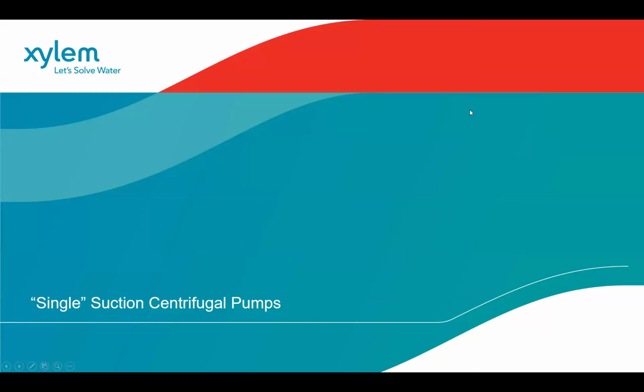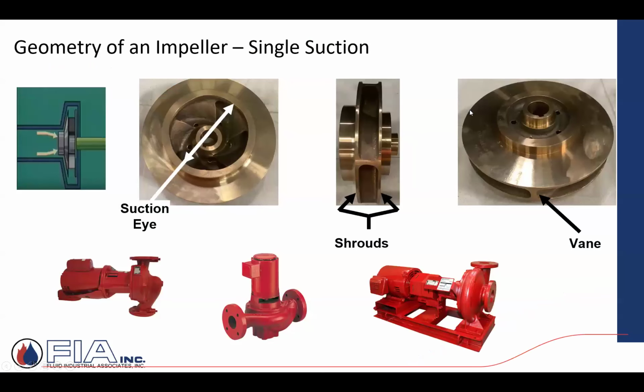So you get into a couple of different style pumps. The first one, single suction. And all they're referring to is that the impeller is known as a single suction impeller. So what they're referring to is all of the water enters into the eye. In this case here, on this top left picture, where the arrows are pointing, that would be the eye to a single suction impeller. Water's entering into that eye and then is rotating along these vanes to its outer edge. You can see the picture on the far right of these, the picture of the tip of the vane.